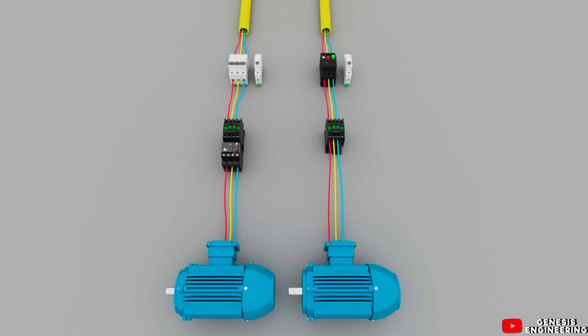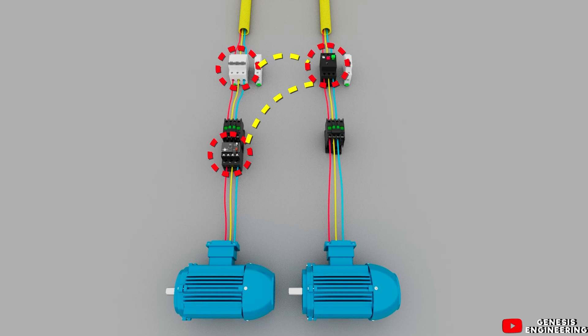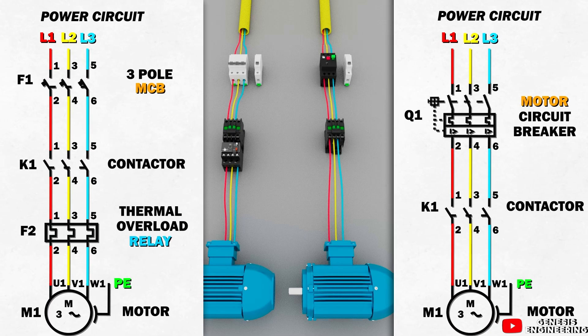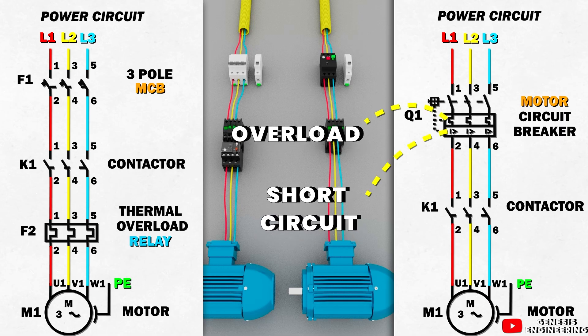We can already see that in the circuit with the motor circuit breaker, the 3-pole MCB and the thermal relay were not used — as I said earlier, the motor circuit breaker replaced both the MCB and the thermal relay. Also note that the motor circuit breaker symbol on the power diagram is different from the 3-pole MCB symbol. On the motor circuit breaker symbol we have both the short circuit protection symbol and the adjustable thermal overload protection symbol.